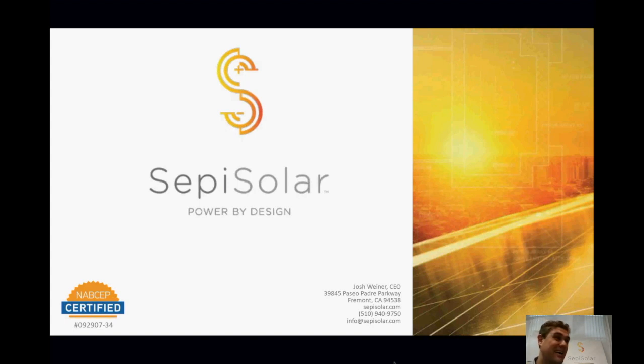Also, you can go with the line side point of connection. For those of you who simply can't meet the 120% rule, can't create enough load calculations, can't derate the main breaker enough, or can't upsize or upgrade the bus bars or service panel itself, you can always get around it with what some call a supply side point of connection, where you bypass the panel entirely. You connect the solar and storage asset on the line side of the disconnecting and overcurrent protection means for that service panel or distribution panel.